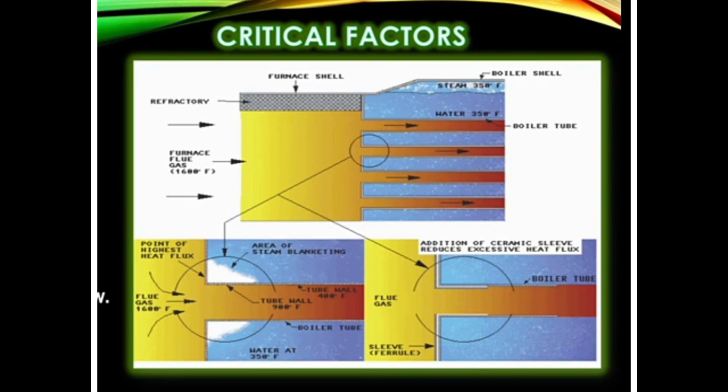One important distinction: steam generating from the surface of the boiler drum where we maintain the level is called normal evaporation. However, steam generating at any corner or part of the boiler tubes is abnormal and is caused by steam blanketing — this is called abnormal evaporation. That concludes today's topic on steam blanketing.